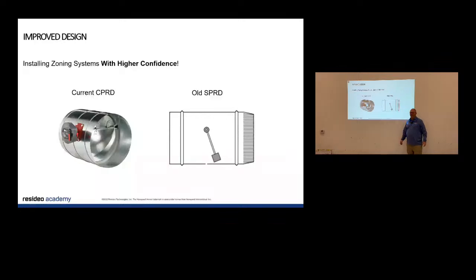And a contractor would go in and they would have to do the same thing. They'd get just the smallest zone calling, the other two bigger zones, or one bigger zone, not calling. And they'd have to slide this weight up and down until it opens and closes. Sounds pretty easy to do, right? But about 85% of them out there didn't have a clue how to set that.